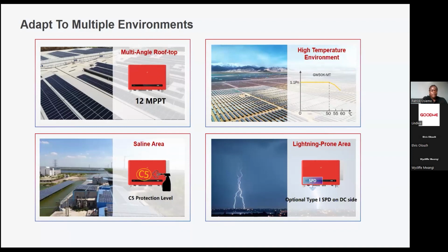But this one being, in case you're doing ground mount installations or you're doing installations on roofs facing different terrains, different angles and such, we have numerous MPPTs and each MPPT can work independently. So if your roof or your string faces a different direction, that MPPT will be tracked and ensure that it's outputting maximum depending on its angle.